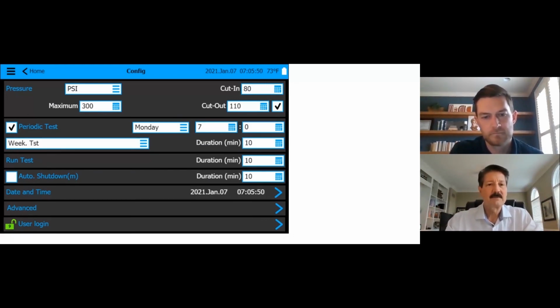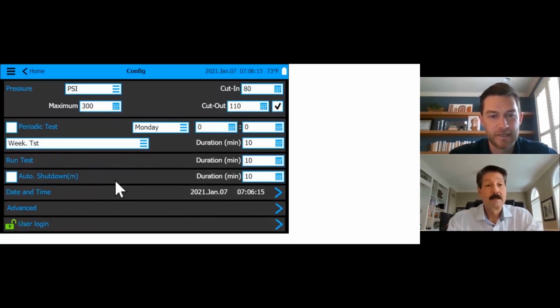I don't like doing it automatically, because code wants you to be there when the unit is running. They want you to be in front of that system. So I know it's required, but I don't really see a lot of people using it. But I just wanted to point it out that it's something that's standard in all manufacturers of fire pump controllers. Yeah, that's a requirement. But then if you're in the room, might as well just push the button anyway. Yeah. Instead of setting it up automatically. Agreed. So again, the run test we show is 10 minutes. You could change that if you want.